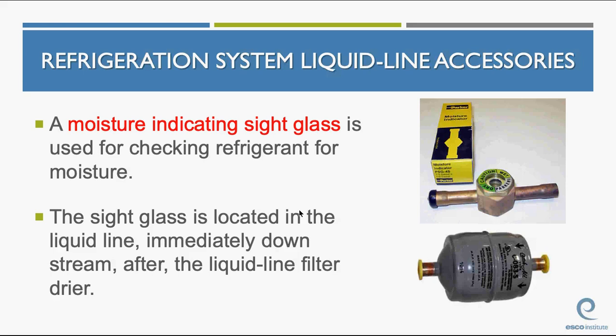It's strictly for moisture. The sight glass is generally located in the liquid line immediately downstream, which means after the liquid line filter dryer. By the way, notice the arrows on this. That's the direction the refrigerant is flowing. Or should be, unless someone put this in backwards.